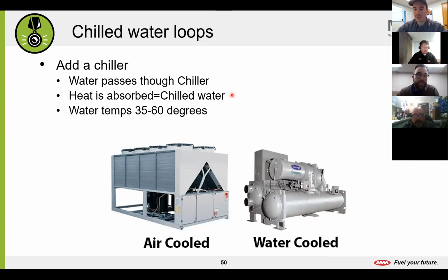We're going to talk about chillers. And here it'll show you an air-cooled chiller and a water-cooled chiller. So we'll dig into that. You can see on this air-cooled chiller here, we've got this big refrigerant coil with fans on it. That's our condenser. That's where the heat that we're absorbing from the water comes up into this coil. This fan is going to run outside air through the coil, and we're going to reject heat from that refrigerant into the air and just get rid of it. We're just heating up outside. We don't care if we're heating up outside.